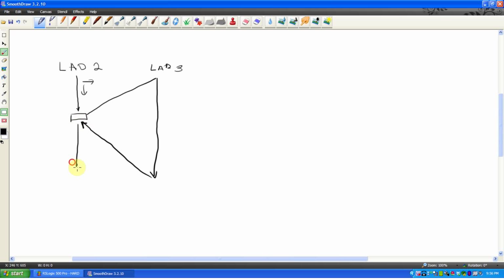where it continues the rest of the way, and at the end of ladder 2 there must be an end command. The scan must always start at the top of ladder 2 and must always end at the end command of ladder 2. But we can have it jump out, do something, and come back. And again, in this subroutine, it's going to scan left to right, top to bottom. So it just continually runs this pattern now, this loop.